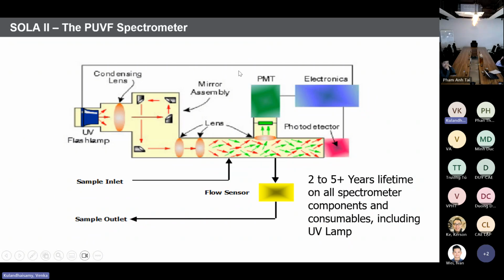Yeah, this is the PUVF spectrometer bench, how it looks like. Here is a simple flow diagram. You can see the sample inlet through a flow sensor. Sorry, the sample inlet goes to the chamber of the PMT bench assembly. The PMT bench assembly has a UV lamp, then some filter mirrors, then the PMT assembly, and then a photodetector. There is one feedback electronic circuit.